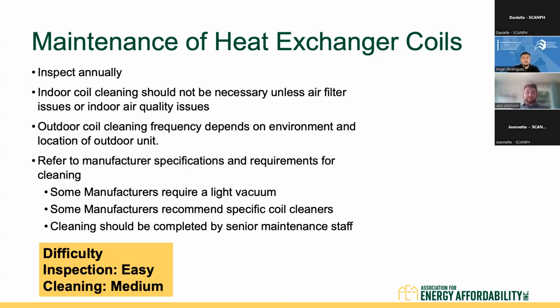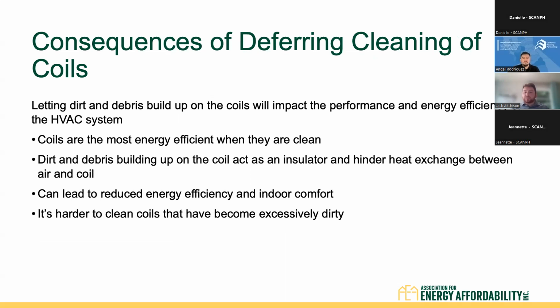Next slide, please. So, consequences of deferring cleaning of coils. Letting dirt and debris build up on the coils will impact the performance and energy efficiency of the HVAC system. Coils are the most energy efficient when they are clean. Dirt and debris building up on the coil can act as an insulator and hinder heat exchange between air and coil, which can lead to reduced energy efficiency and indoor comfort. It's also harder to clean coils that have become excessively dirty.